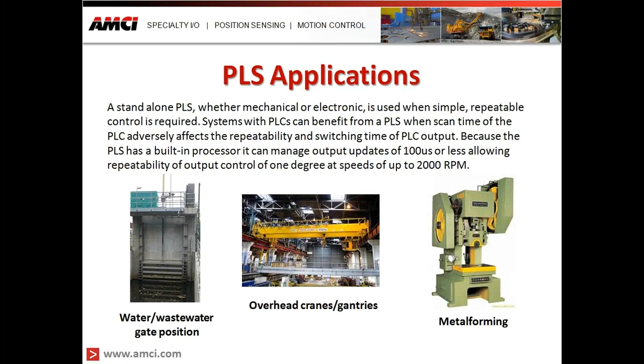Typical PLS applications include standalone use where simple, repeatable control is required. For example, at remote locations like water treatment or wastewater facilities, sluice gates that need to open and close can use a PLS with a rotary sensor to monitor position and control the motor. Overhead gantry cranes with multi-turn sensors can use programmed set points to automate crane control, firing a motor on and off to stop at specific positions, as commonly seen in plating lines.